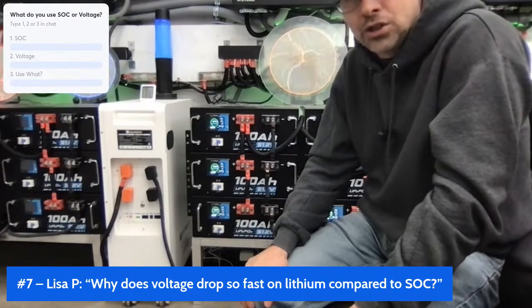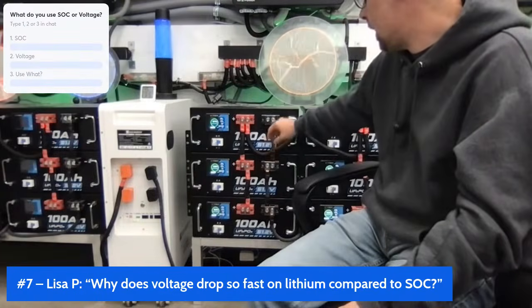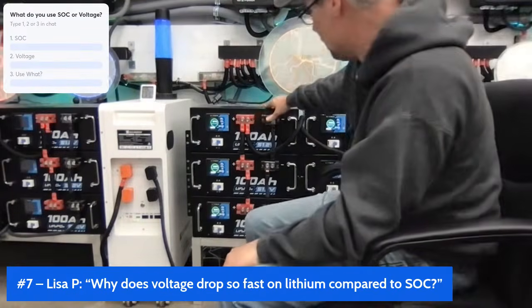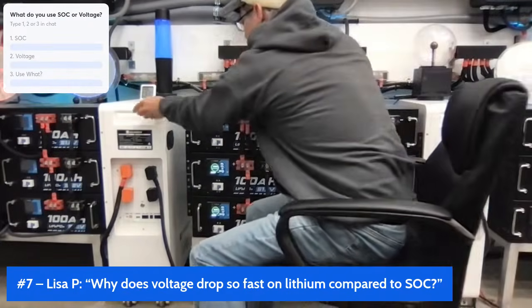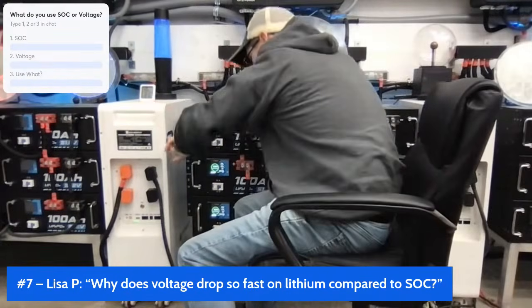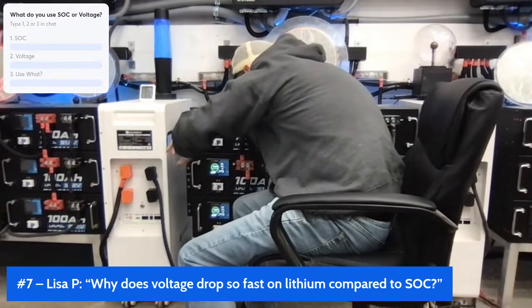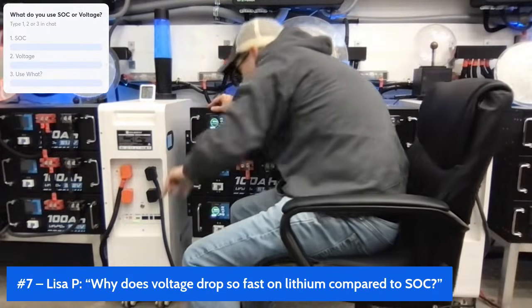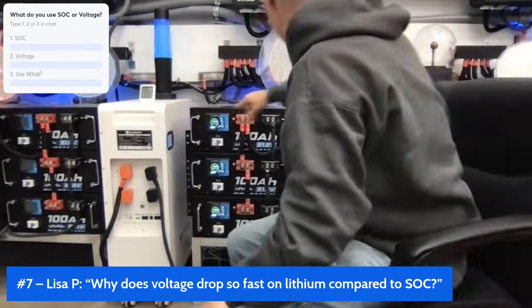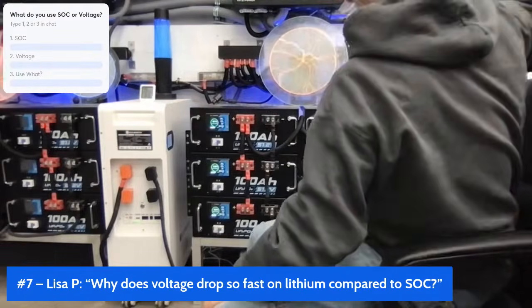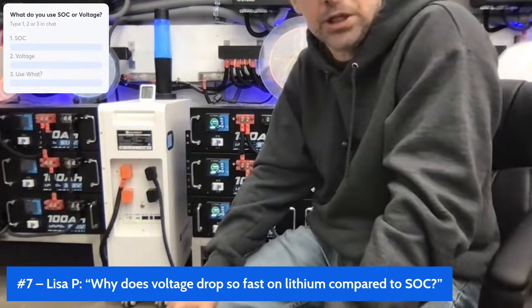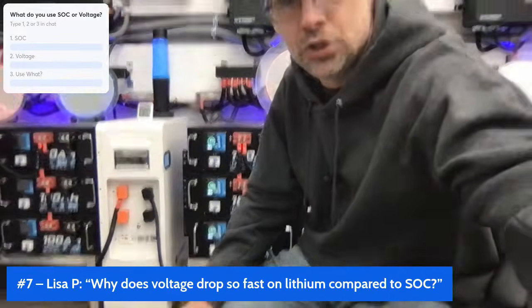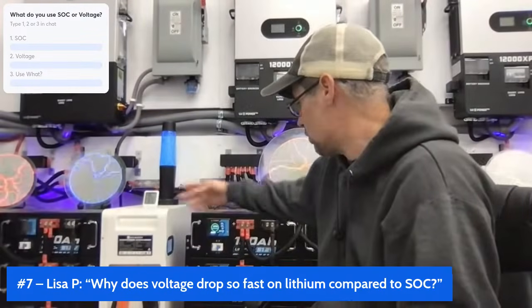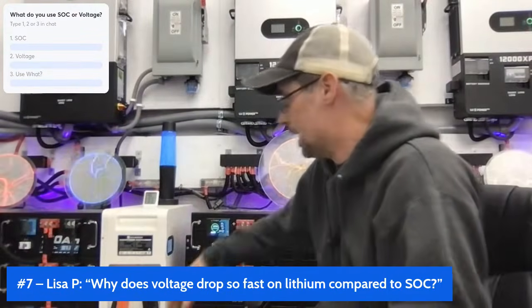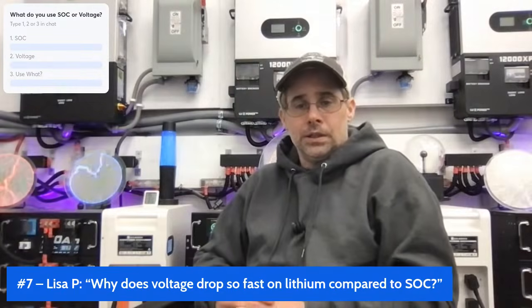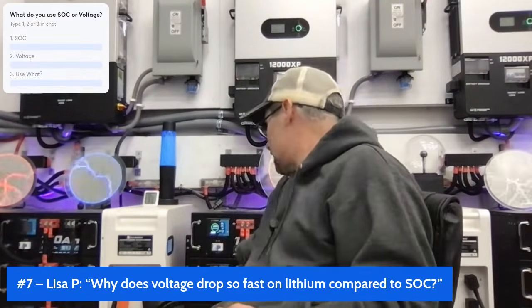Now, where SOC fails is when you have different size batteries. You could see these say 97, 98. And if I pull this one out and look at it real quick, it says this big one is 80%. And there's another 280 over there and another 280 over there, and all those are probably going to read 80% as well. So if you have different size batteries, the SOC is for the battery, but not necessarily the whole bank. But kind of going back to it, wire size matters.